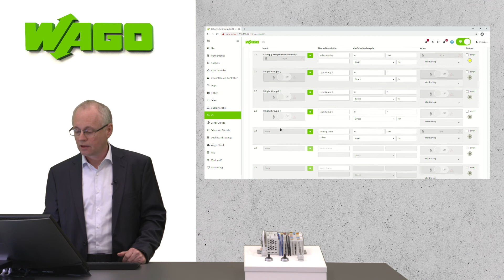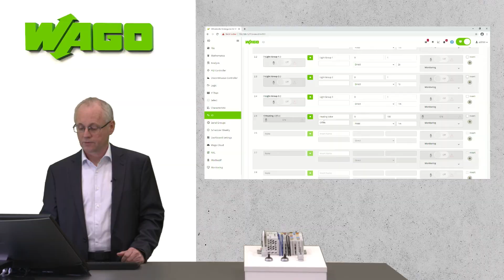Therefore, I will go back to the I/O configuration, select the digital output, the heating valve, and use again the data point catalog to connect the output of the PID controller to the heating valve.